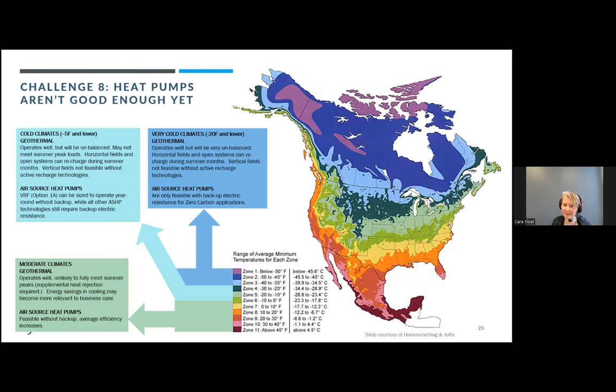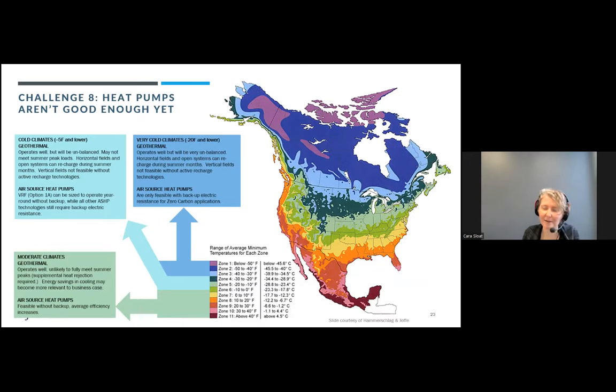And finally, challenge number eight: heat pumps are not good enough yet. We know that if we were working in Texas, we could heat every building we worked in and would never have to go to electric resistance backup. In Toronto, we have access to cold climate heat pumps full of R410A refrigerant with high global warming potential, or we have access to low GWP heat pumps at price points that are three times the cost. So all of these challenges just mean there isn't a wide enough variety of products available.